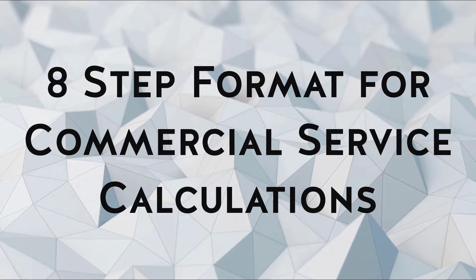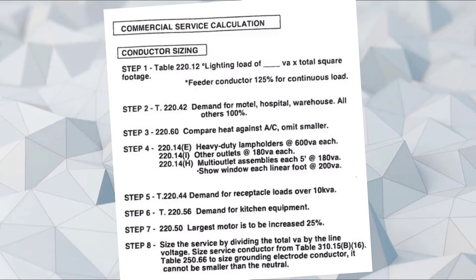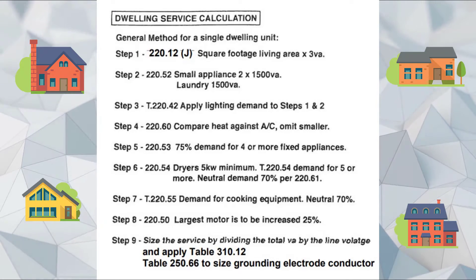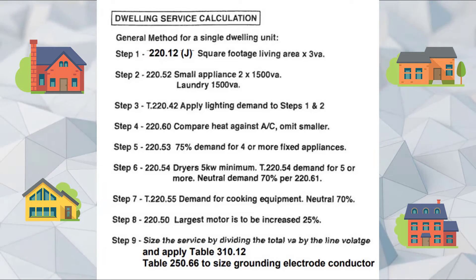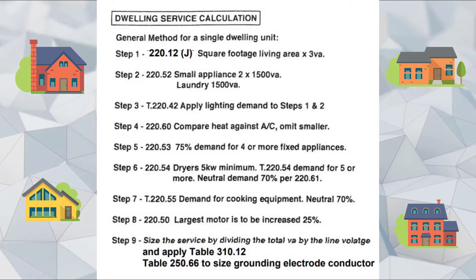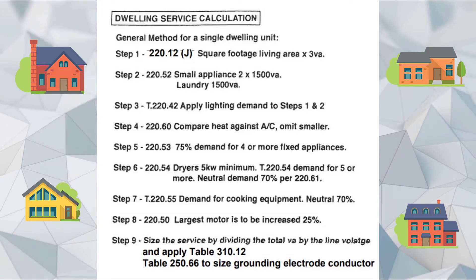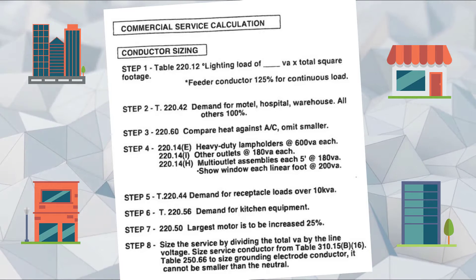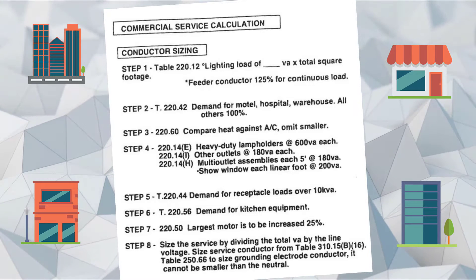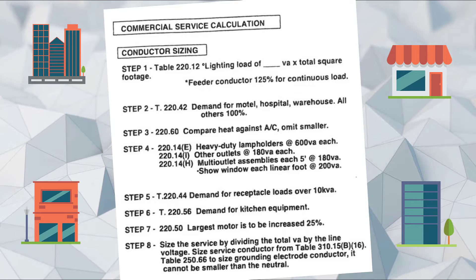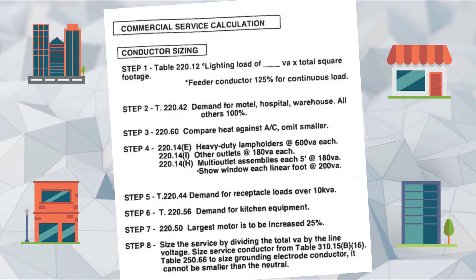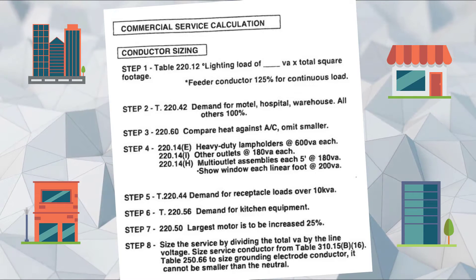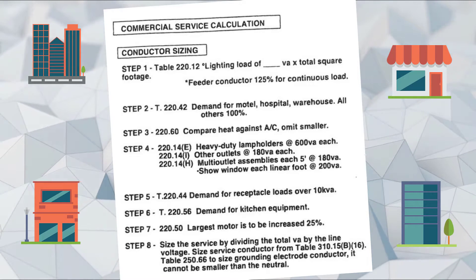The 8-step format for commercial service calculations is different from dwelling service calculations. In a dwelling unit, you get to derate to a high rate because you're not going to have all the lights on or use all the load at any given time. In a commercial application, you're going to be using continuous loads a lot — think about a retail sales area where lights are on 24 hours a day, air conditioning is running constantly, and refrigeration and freezing equipment runs constantly. So the loads are heavier and more constantly used.